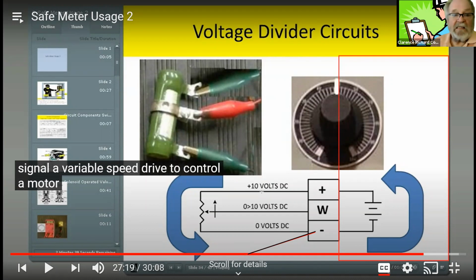So then I'm going to be asking if I run my pot up and down there and it doesn't change the speed, it could either be the fact that you didn't give that VFD a run signal, but now you check, yeah, I did give a run signal. So that's part of what makes a VFD work. If the output's not there, check its inputs.